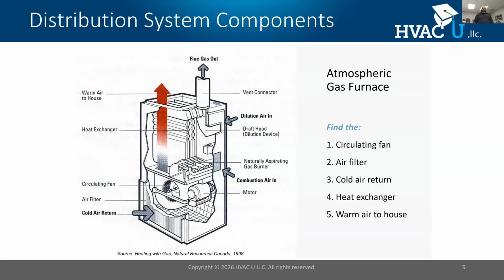All right, looking at our distribution system. We're going to start at the blower, which is a point of pressure where we increase the pressure and circulate the air through the duct system. In the air handler or furnace, or if we have an attached air conditioning system or heat pump, we're going to have a series of heat exchangers. Depending on your mode, that air is going to travel across those heat exchangers and go into the distribution system. Now, the point of the duct system is to get the air from point A to point B really quick without a large pressure drop or temperature losses. If we don't have the duct system sized properly or balanced, or if we have errors like not duct sealing or insulation problems, we're not going to achieve those goals.